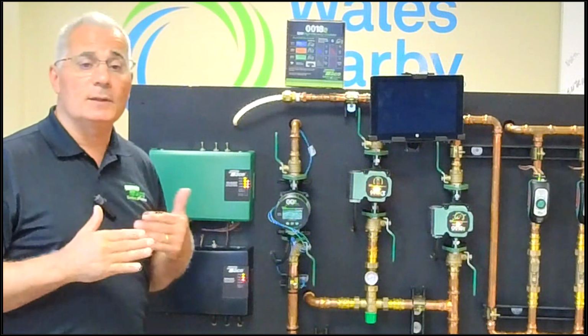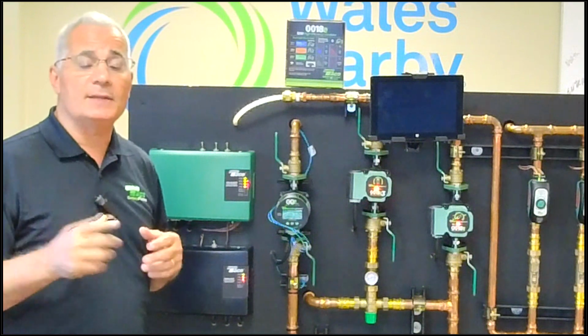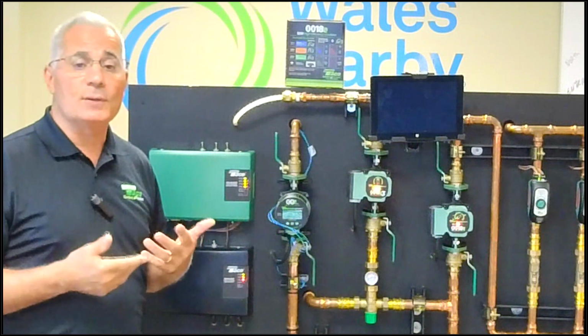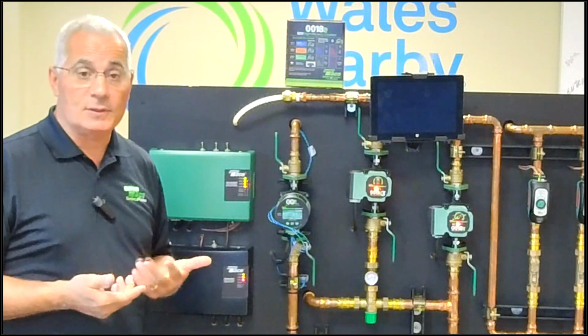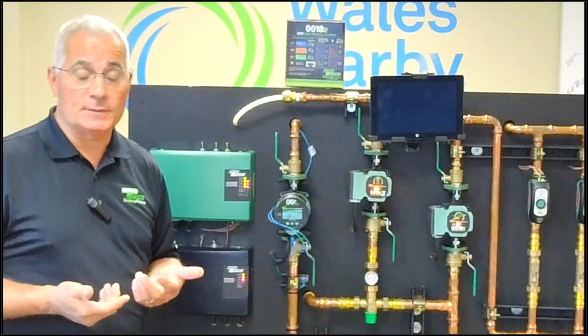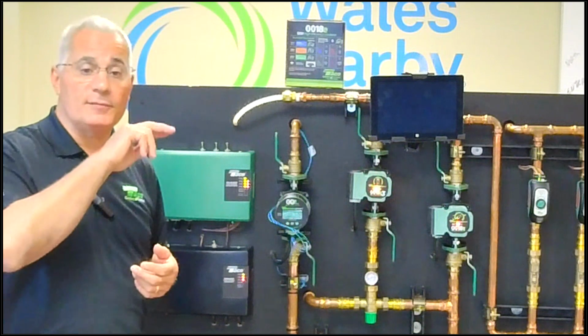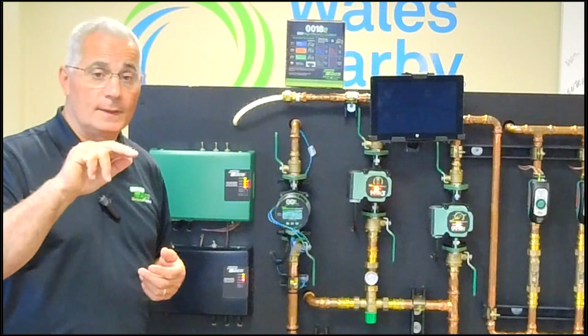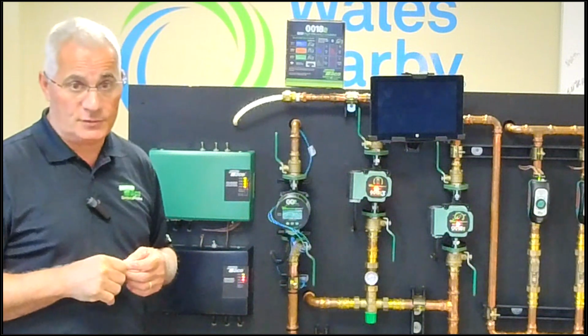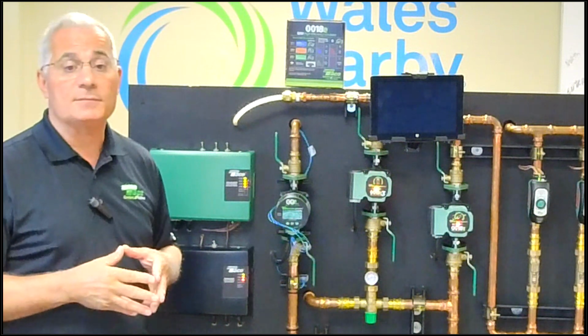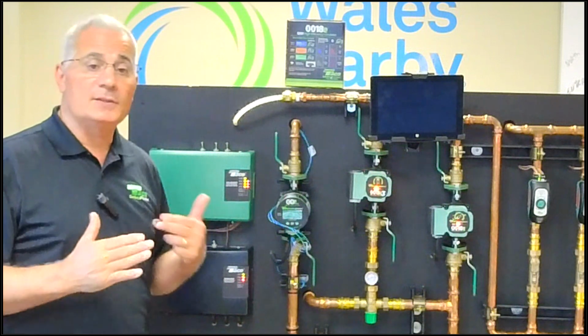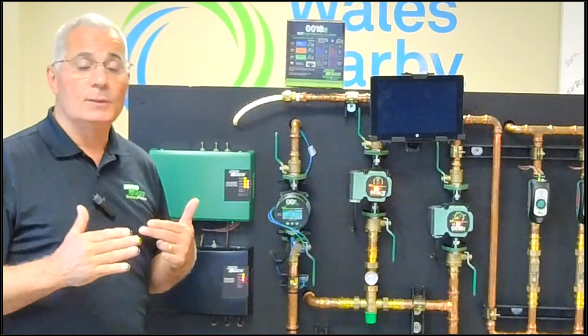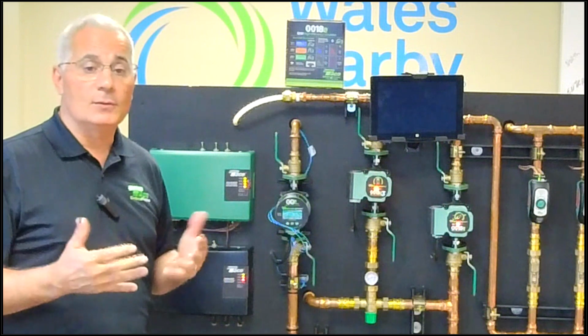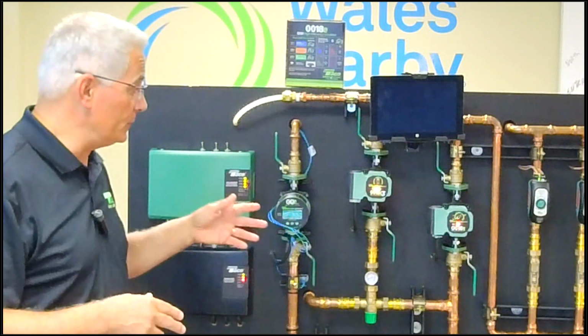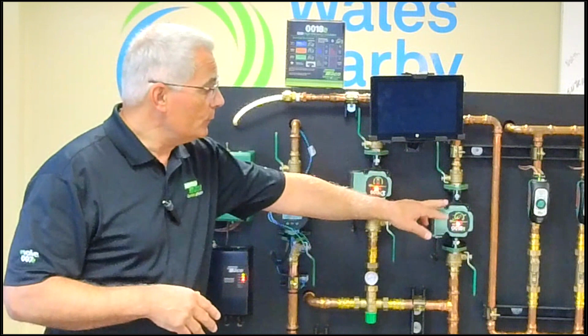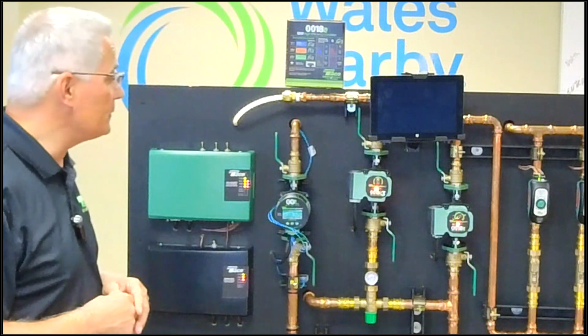So as zones open and close, it'll run along that 5 feet of head. And as it does that, it's going to lower its amp draw. Again, an energy saving feature. If we are on medium speed, we're going to follow 10 feet of head out to 8.25 GPM, which is 82,500 BTUs. And as zones open and close, we will vary our amp draw and lower our energy consumption. I will be able to show you that when we go back to this 0018E3.